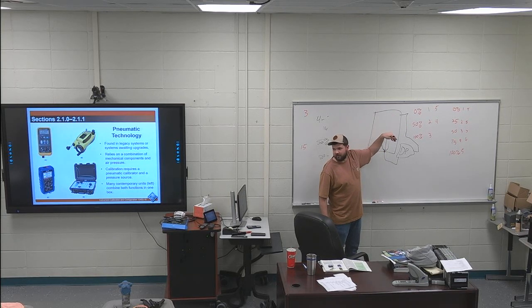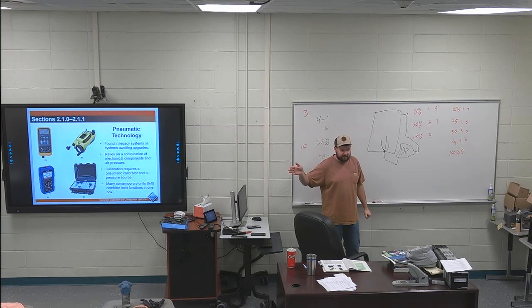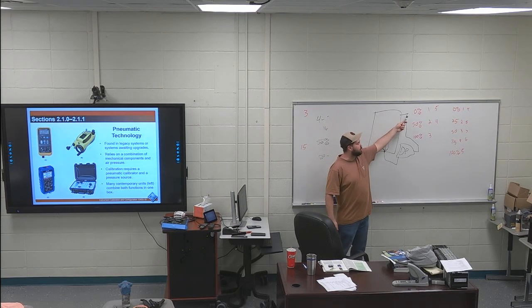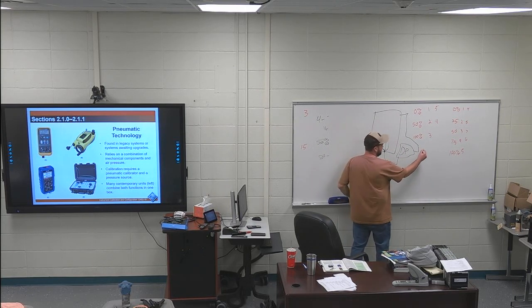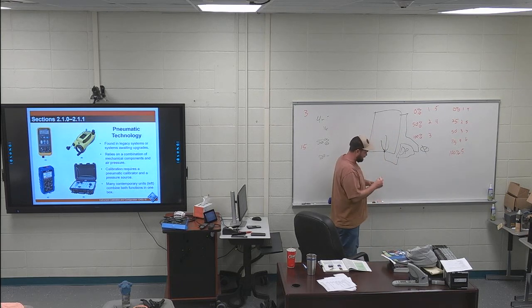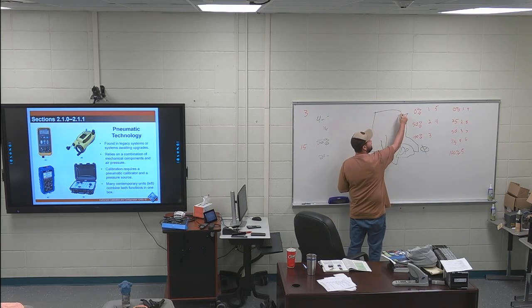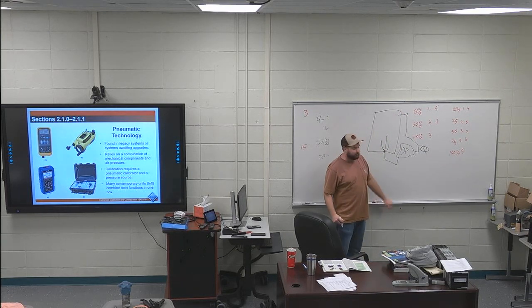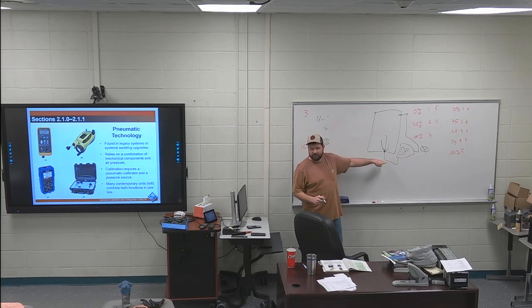If whatever's in here does condensation, like the temperature outside now, we're flipping 25 degrees outside and then it's 65 degrees today, stuff is sweating today. And this would build up with condensation. Well, this is my 0, right? That's my 0 right there. So if I get a little bit of stuff in there, my 0 is not going to be right. And this isn't going to read the level of the tank right.